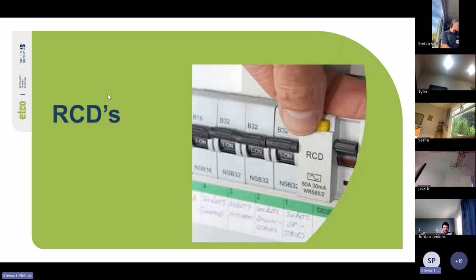So the MCB has two mechanisms, the bimetallic strip and the solenoid coil. As the video said, the bimetallic strip takes a while to heat up and activate. So if there was a spike of, say, 60 amps flowing through a 6 amp breaker, it would take ages for the bimetallic strip to heat up and bend. In the meantime, there could be fire or shock hazards apparent. So we need to make sure they trip properly.